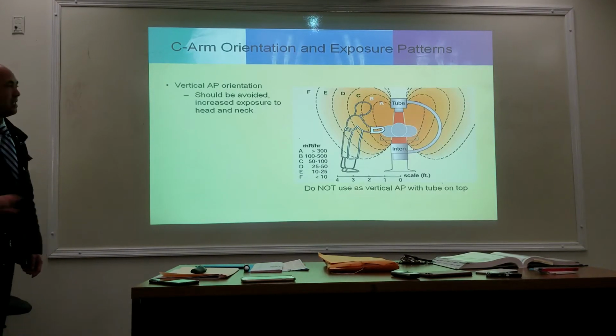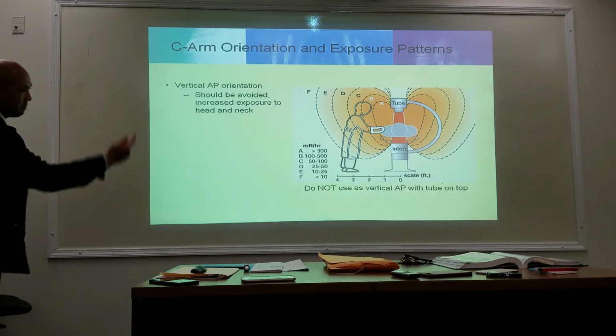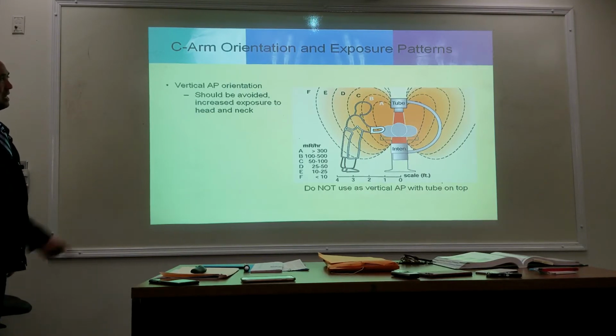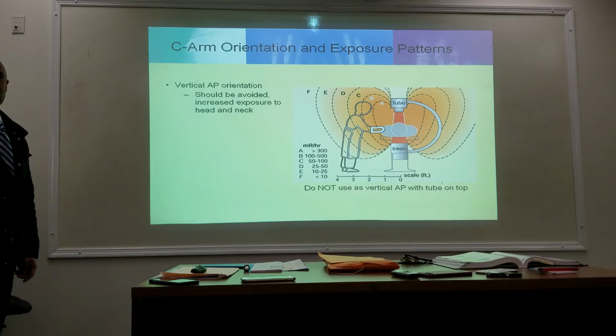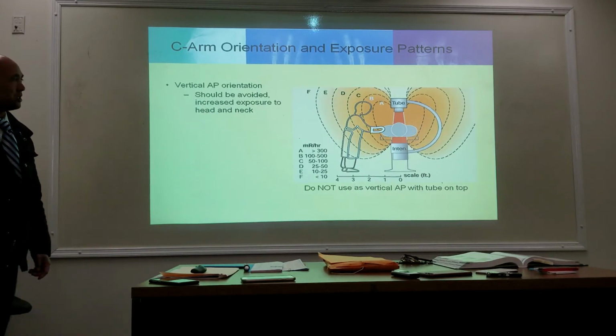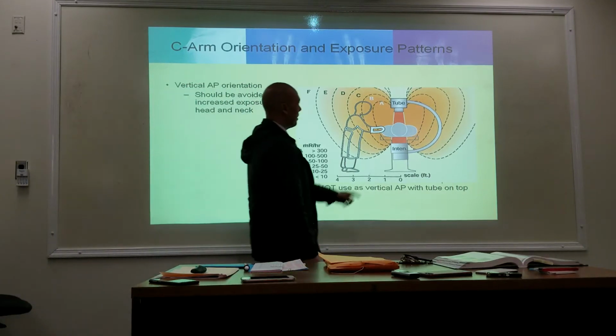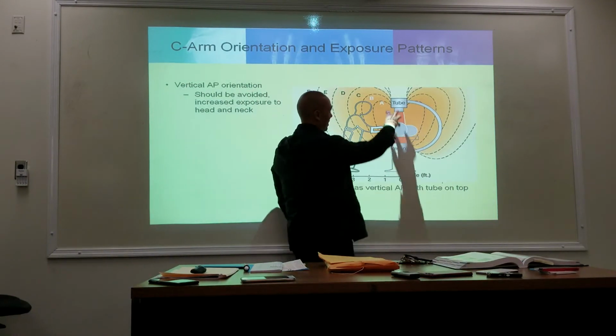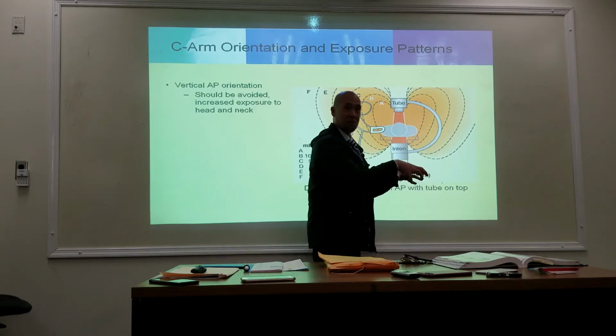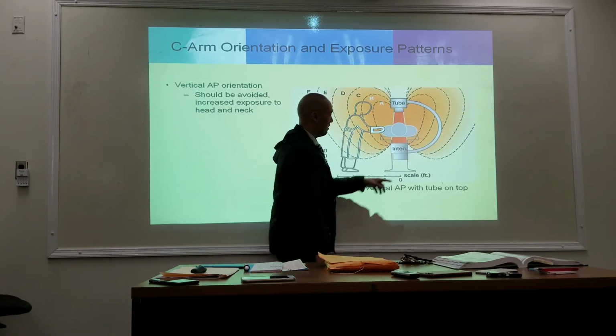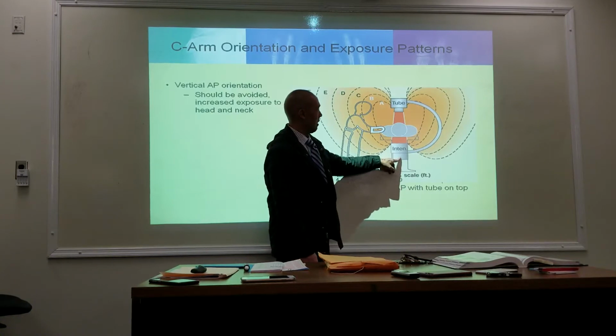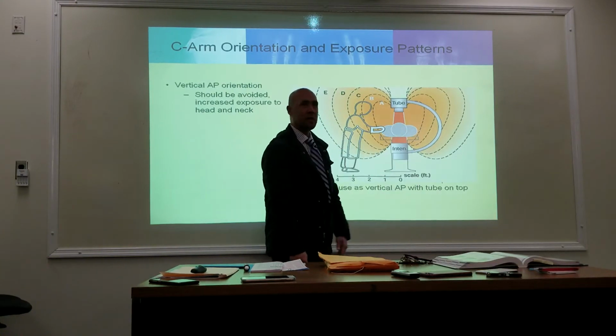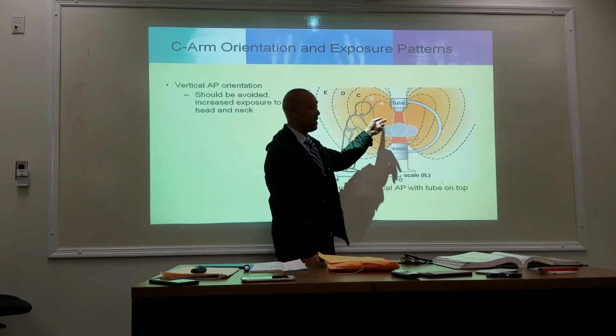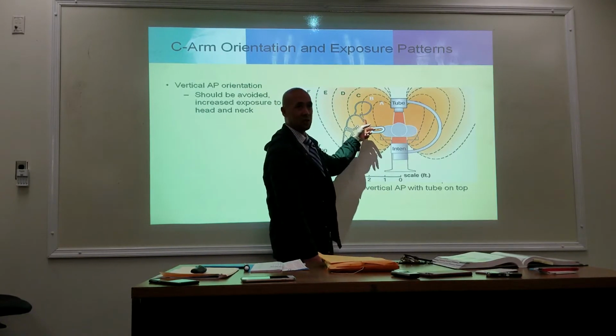Okay, and this is the opposite. Now you have the x-ray tube on the top, image intensifier on the bottom. Again, this is probably the worst position that you can be in. And I tell doctors that too, because sometimes they want the x-ray tube up here because it's smaller. They're able to work a little bit closer with the patient. The image intensifier is bulkier. So let's say they put the x-ray tube on the top. I would say, well, why not? I said, because you're going to blast your eyes, you're going to blast your thyroid. You're going to get a larger dose.